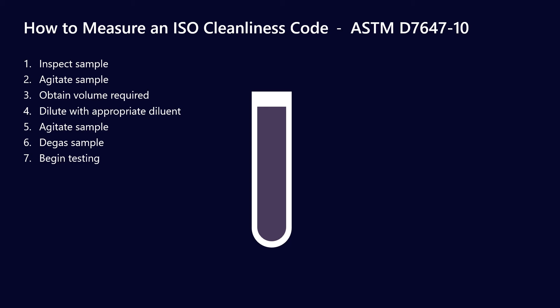So the ASTM method here is really about sample preparation as opposed to a change in the test method. We're still going to measure ISO cleanliness by light extinction — by shining a laser through the sample. But we're trying to prepare the sample in such a way that things like additives, water, air, and sludge are removed from the sample beforehand.